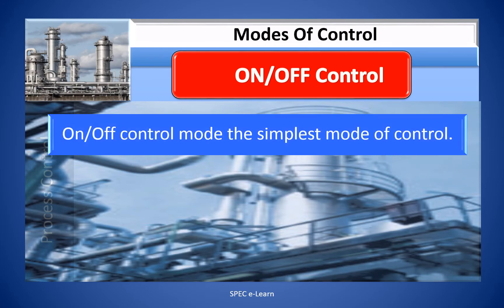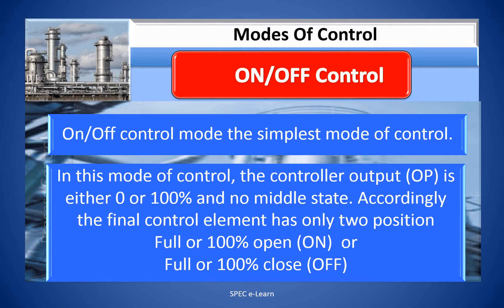Depending on the system to be controlled, one can select one or the other type of control mode. On-off control mode is the simplest mode of control. In this mode, the control output (OP) is either 0 or 100% with no middle state. Accordingly, the final control element has only two positions: full or 100% open, that is ON, or full or 100% closed, that is OFF.